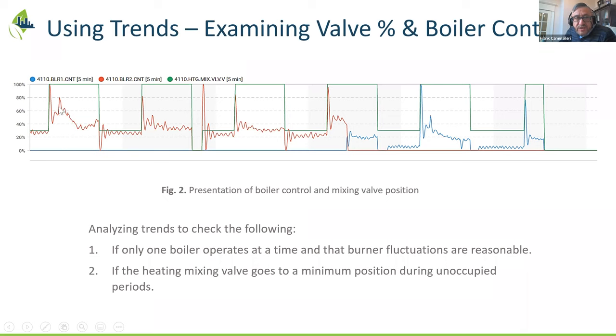You can see the red line here - this is the burner operation of boiler number two, and this is boiler number one. So the first point is that only one boiler is operating - boiler one is off here and boiler two is running. Good, that part works, and the fluctuation isn't unreasonable.